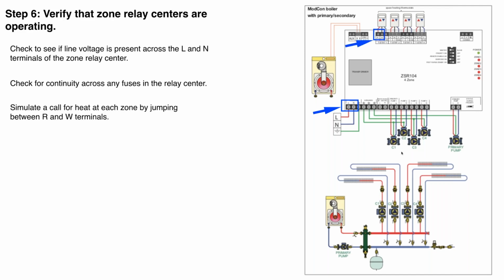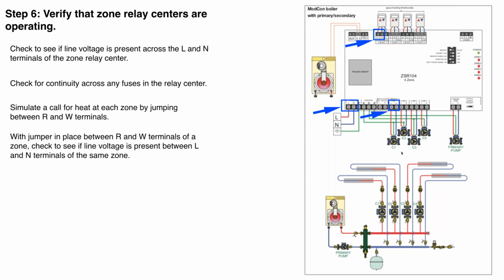You can simulate a call. Again, if you jump between the R and the W terminals, in effect, you're doing what the thermostat would be doing when it calls for heat. You're providing a circuit path between R and W, okay? Jumper in place between R and W, check to see if you've got line voltage down here at the circulator. Okay, so this is the call for heat. If you're not getting line voltage down here, something is wrong in between. It could be a fuse, it could be a bad relay, but something is wrong in between.